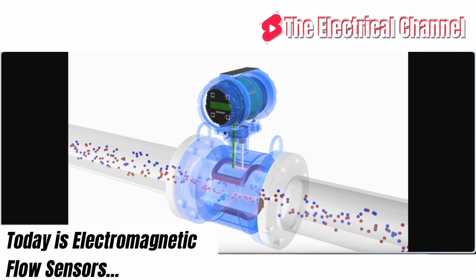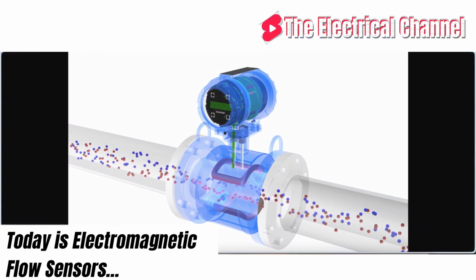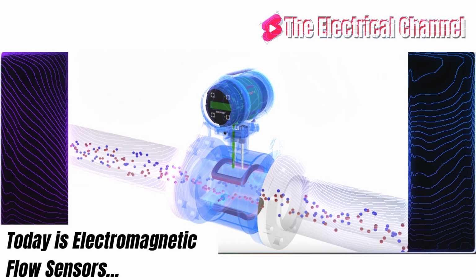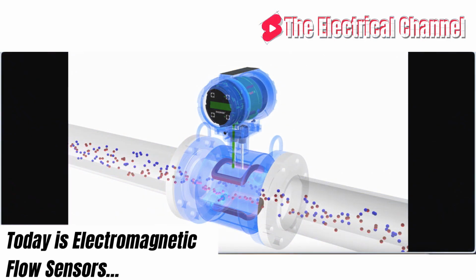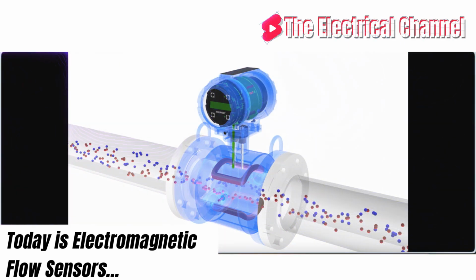This type of sensor has no pressure drop and no moving parts. It is not affected by changes in temperature, pressure, or density, and can handle fluids with contaminants. Each sensor type is available in a variety of sizes and mechanical configurations, with or without a local display.